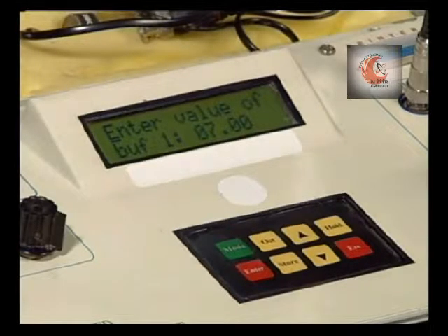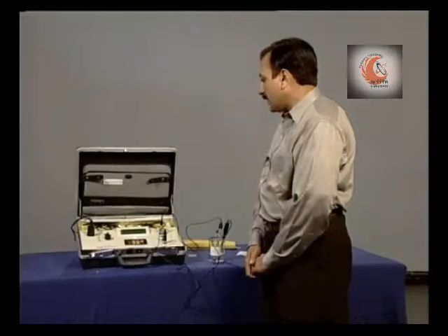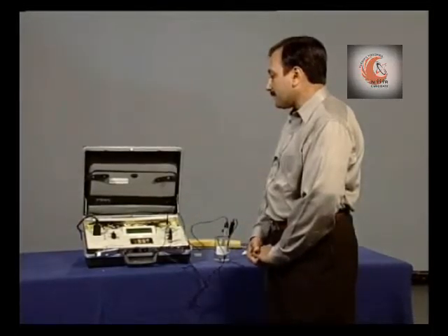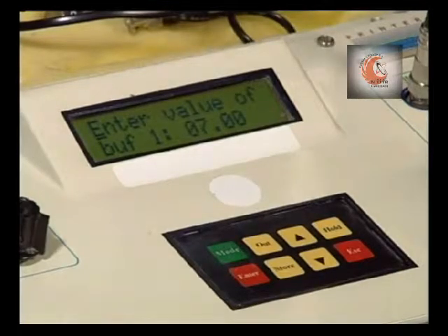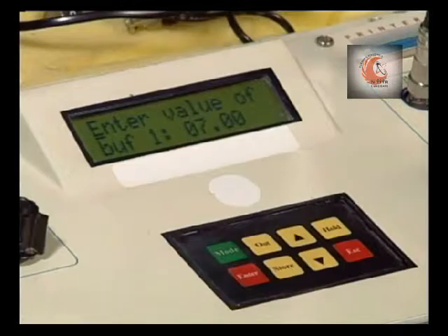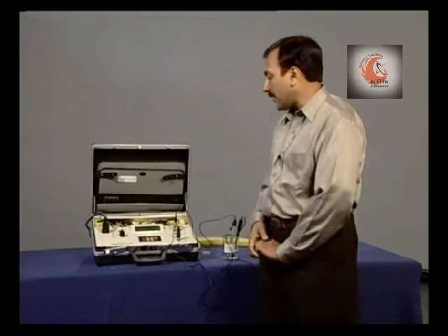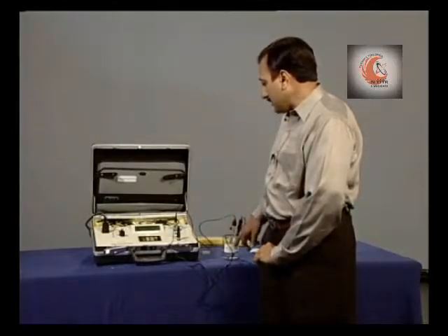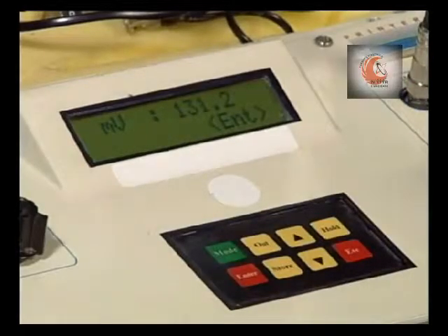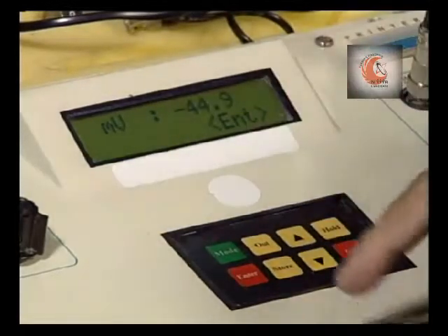Now it displays the pH value of the solution. If it matches correctly with this value, then we will press enter. Otherwise, using these two switches we can increase or decrease the value. Now pH is 7 and the same value is displayed. Let us press enter. So it displays some millivolt.